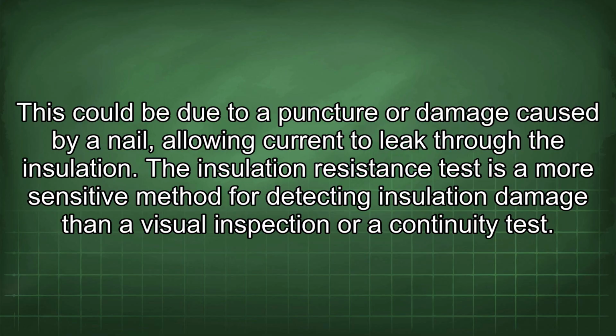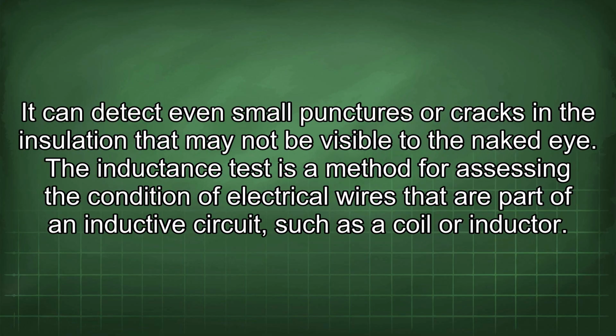The insulation resistance test is a more sensitive method for detecting insulation damage than a visual inspection or a continuity test. It can detect even small punctures or cracks in the insulation that may not be visible to the naked eye. The inductance test is a method for assessing the condition of electrical wires that are part of an inductive circuit, such as a coil or inductor.